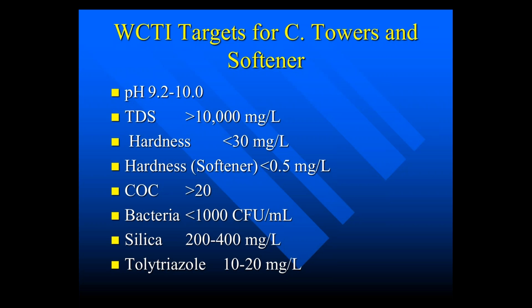The target parameters they want to achieve are: pH 9.2 to 10, total dissolved solids over 10,000, hardness less than 30 mg/L in the tower, hardness at the softener less than 0.5 mg/L, over 20 cycles of concentration. For bacteria their goal is less than 1,000 colony forming units per milliliter. Silica target is 200 to 400 mg/L for mild steel corrosion inhibition, and tolytriazole 10 to 20 mg/L as the copper corrosion inhibitor.